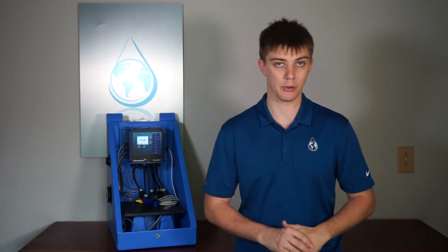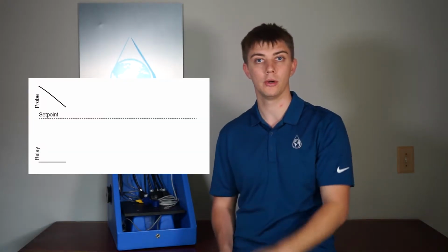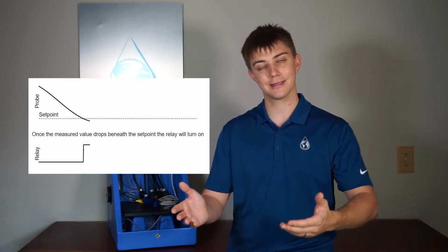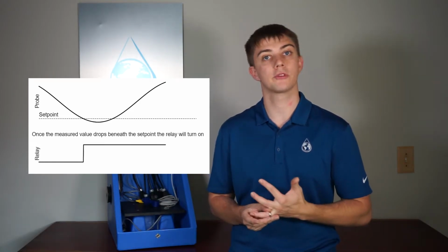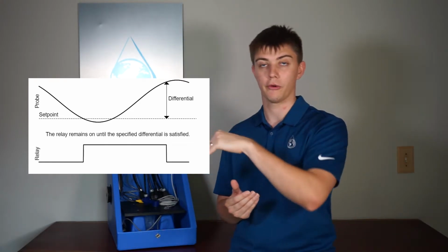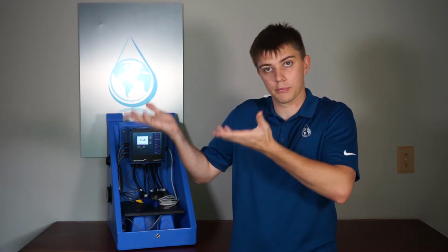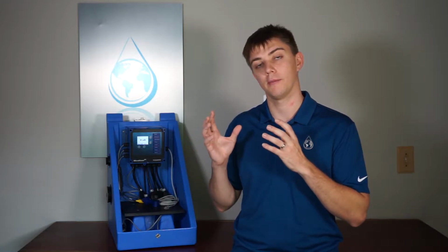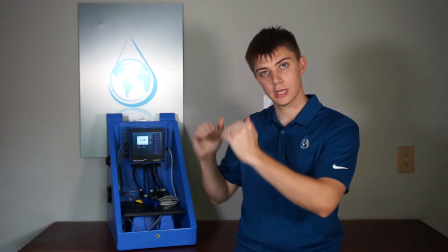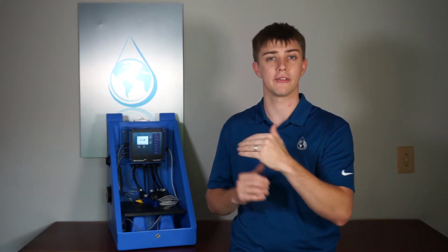Now, if it's a falling set point type, you're doing the opposite. You're waiting for your value to fall below whatever your set point is. Once it does, you then turn on a relay to combat that. You could be turning on a pH pump. It's fallen beneath a value. You need to feed a base, an alkali, to get your pH above a value. Or you could be using a PTSA timer or PTSA probe to keep your PTSA, your trace, above a certain threshold so you have enough inhibitor in your process to keep it under control.